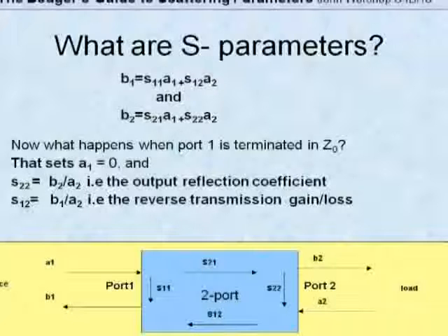So you can do a measurement on a device remotely, so you can get a transistor, put it in a jig, connect up a pair of coax cables, run into the next room with your long coax cables where your network analyzer is, measure the input reflection, output reflection coefficient, gains and losses of that network, and you fully define that transistor right down to its terminals. You don't have to worry about long leads, straggly bits, anything like that.